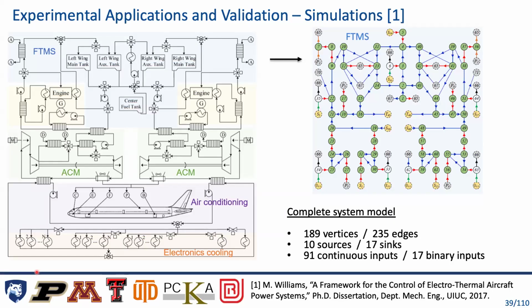We have scaled this up. To my knowledge, this is one of the most complex systems that we've applied graph-based modeling to, with just under 200 vertices and over 200 edges, and a little over 100 controllable inputs, both continuous inputs and on-off valves and various types of binary inputs. In Matt Williams' thesis, we developed models of these systems, both the thermal and the electrical side, and a hierarchical model-based controller based on those models. So the idea here is that we have scaled this up. We believe that could scale further, and it's all just based off of this modular modeling.